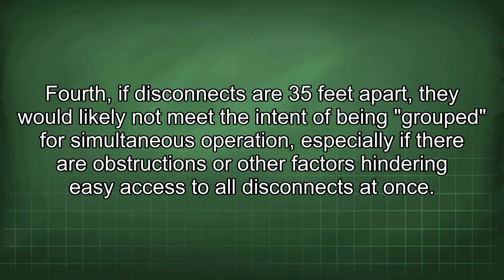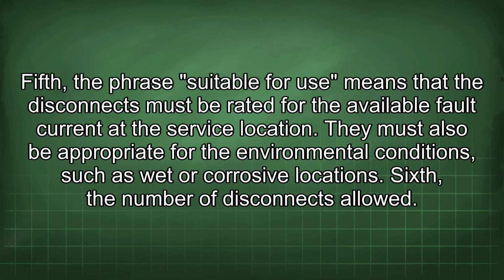Inspectors often interpret this to mean within arm's reach or a few feet of each other. Fourth, if disconnects are 35 feet apart, they would likely not meet the intent of being grouped for simultaneous operation, especially if there are obstructions or other factors hindering easy access to all disconnects at once. Fifth, the phrase "suitable for use" means that the disconnects must be rated for the available fault current at the service location. They must also be appropriate for the environmental conditions, such as wet or corrosive locations.